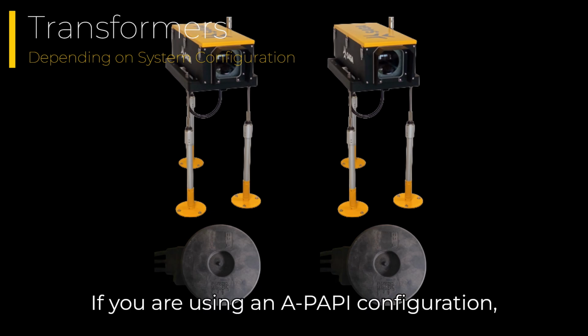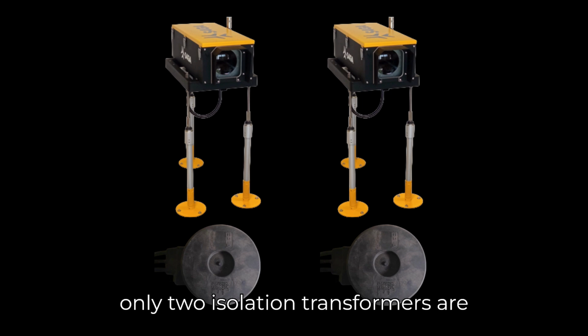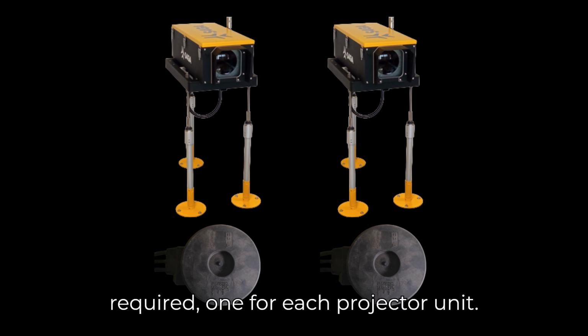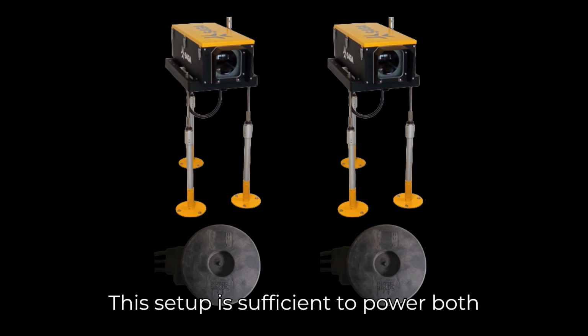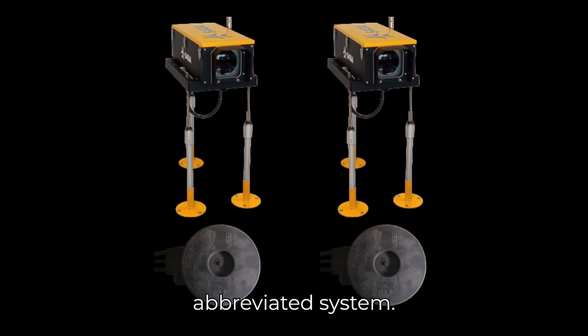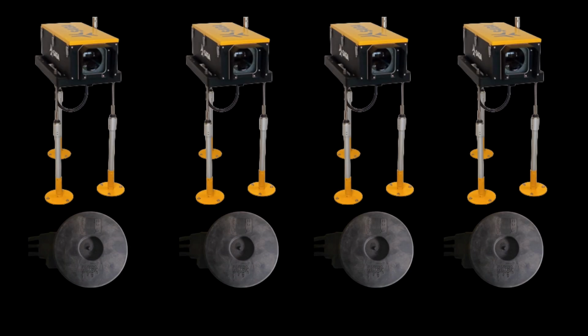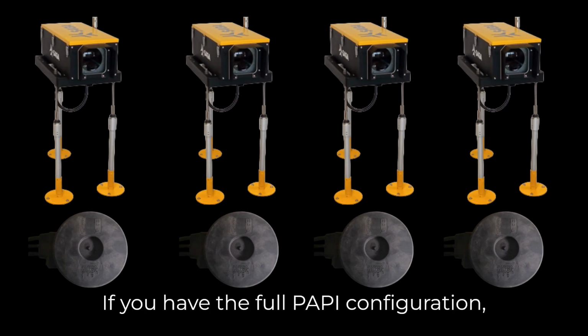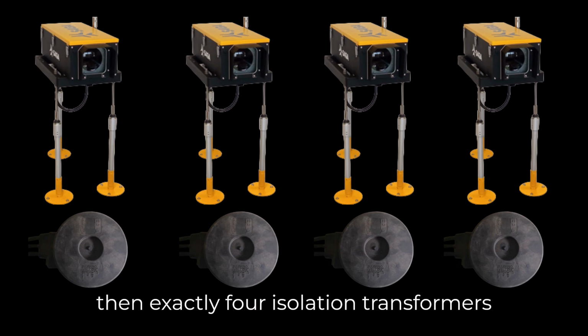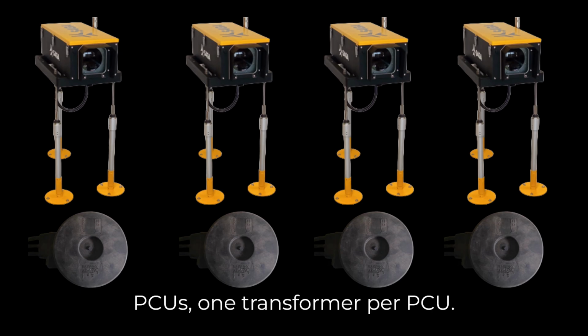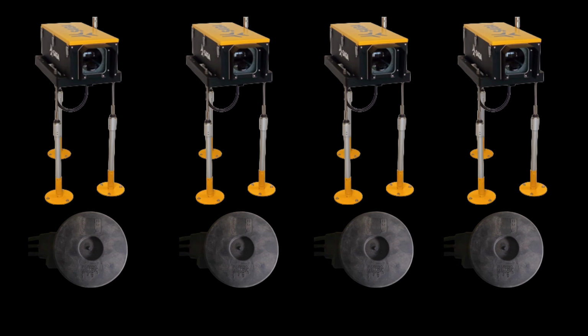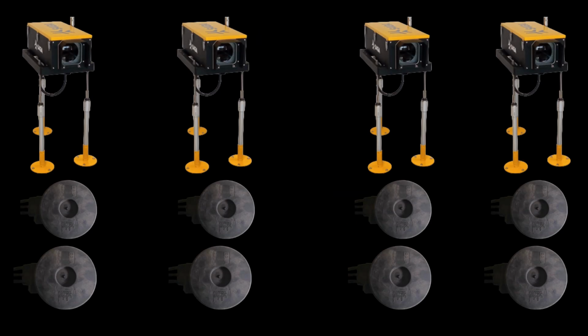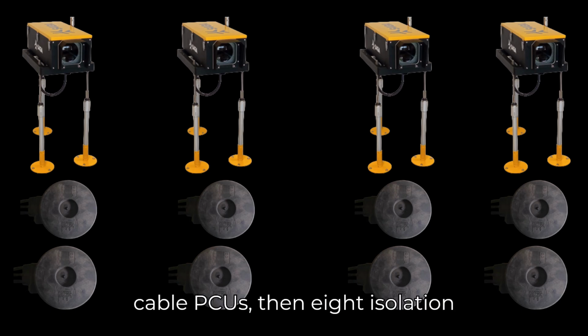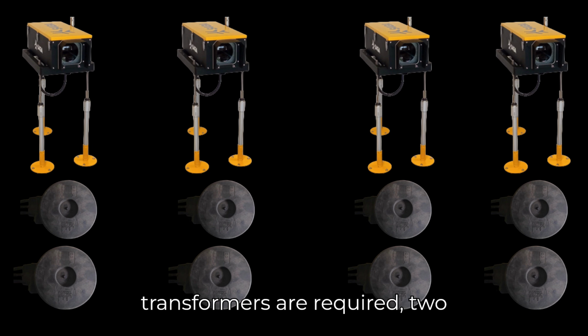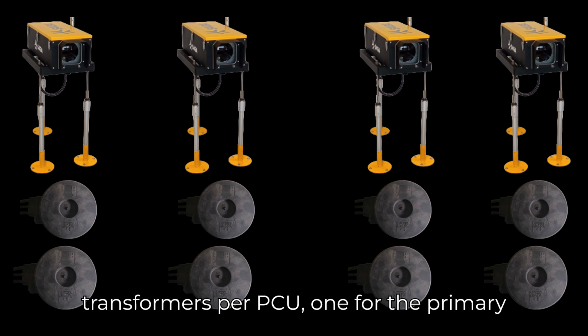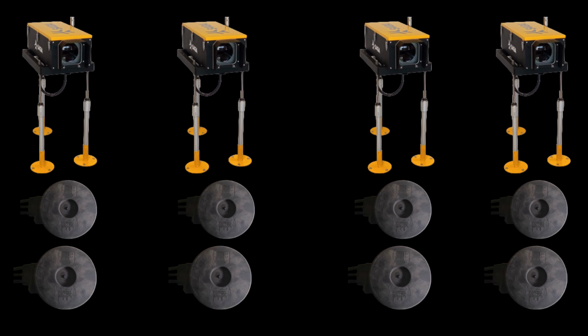If you are using an abbreviated PAPI configuration, only 2 isolation transformers are required, one for each projector unit. This setup is sufficient to power both units and ensure proper operation of the abbreviated system. If you have the full PAPI configuration, then exactly 4 isolation transformers are required when using single-cable PCUs, 1 transformer per PCU. If your system is equipped with dual-cable PCUs, then 8 isolation transformers are required, 2 transformers per PCU, 1 for the primary power circuit and 1 for the secondary.